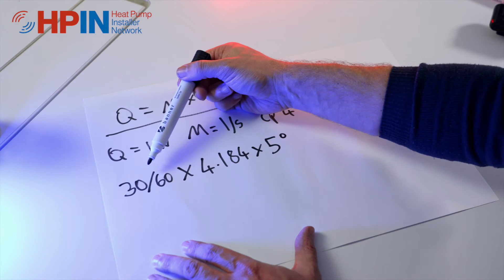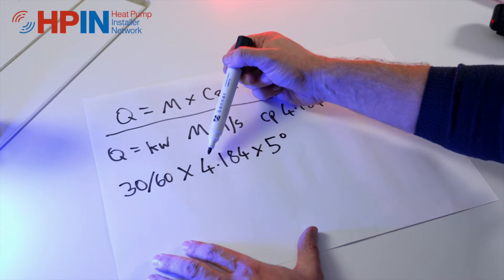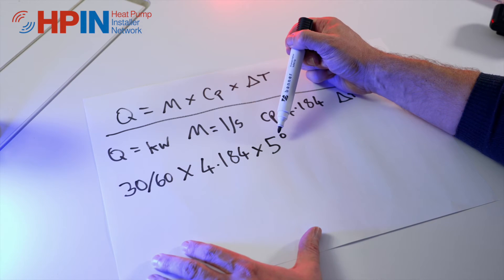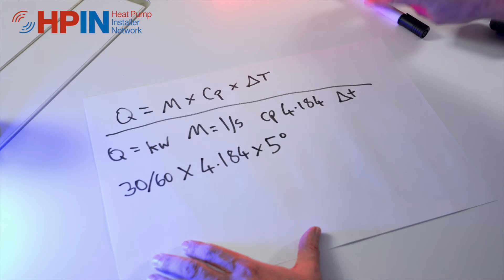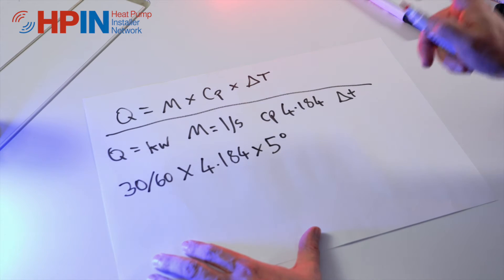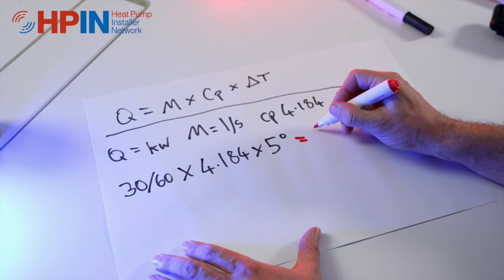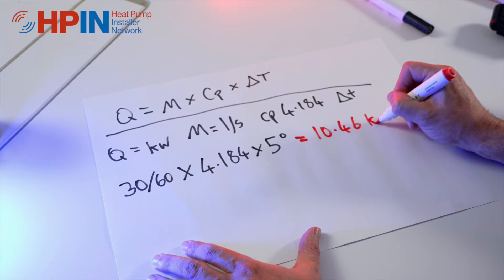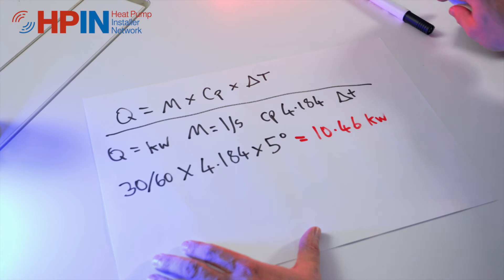So my 30 divided by 60 times my specific heat capacity of water times my 5 degree delta T is going to give me 10.46 kilowatts. So that's where I'm starting from.